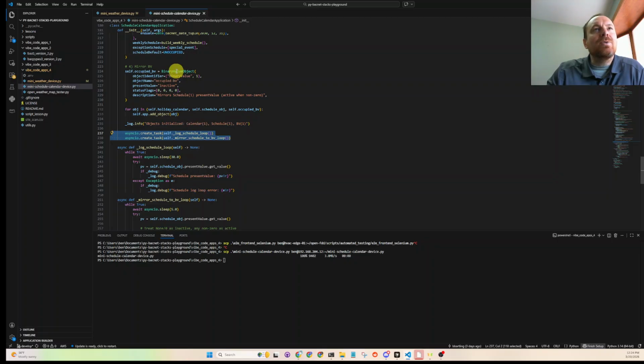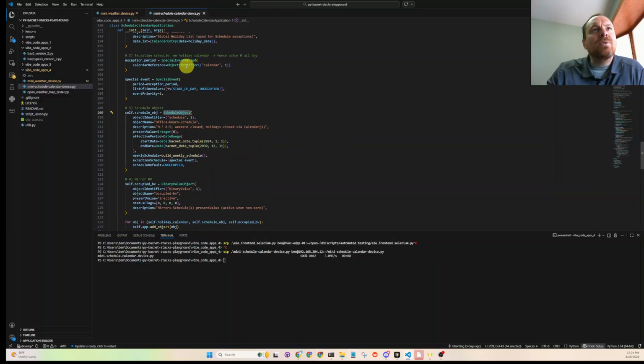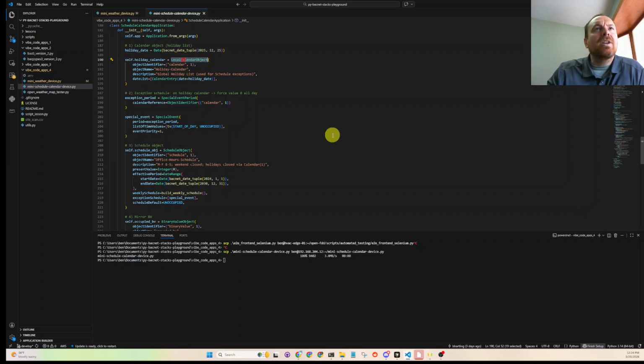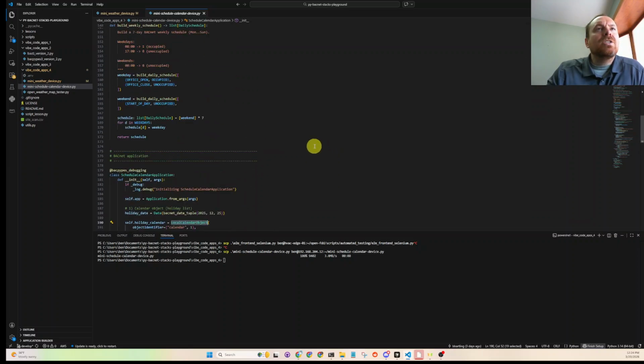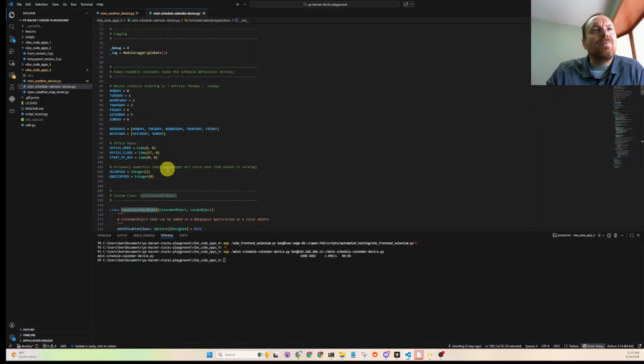The only thing we're doing now is schedule objects and local calendar objects. So we kind of just have to pretend that this is a building automation GUI, and our equipment is scheduled to run on weekdays from Monday through Friday, 8 to 5. So that's what we'll see in the BACnet data.